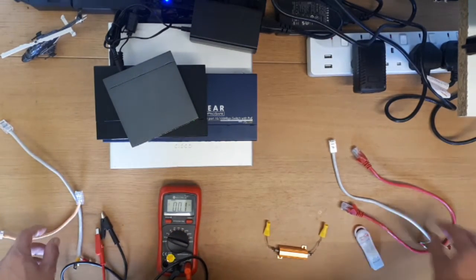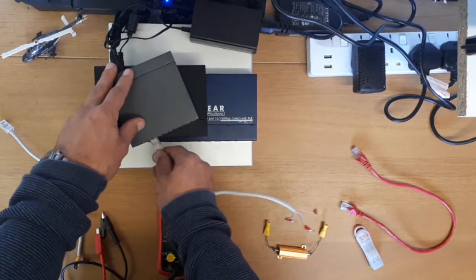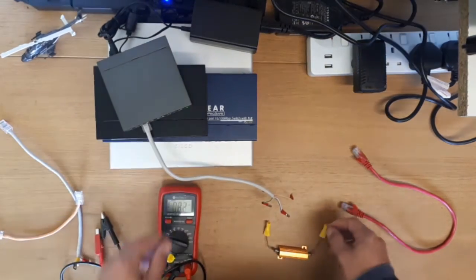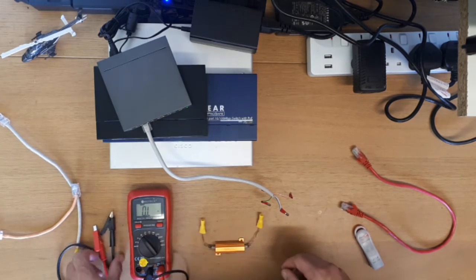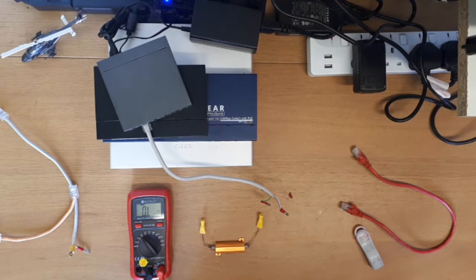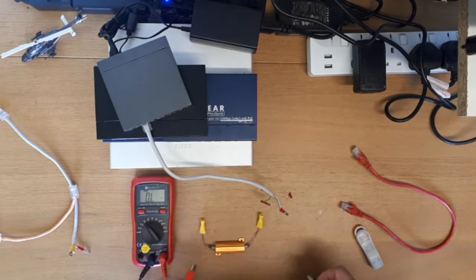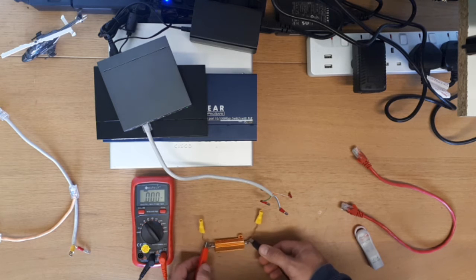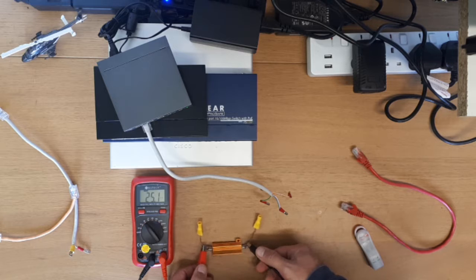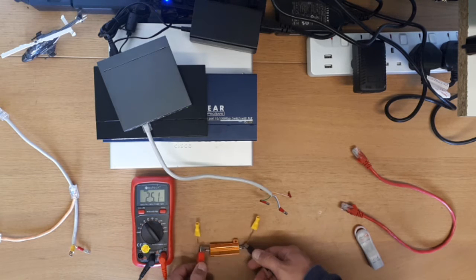So what we're going to do is connect this cable here. Now this resistor here is 25 kilohms. I've just turned this to resistance, and I'm going to demonstrate that this is a 25 kilohm resistor. Okay, 25.1 kilohms, which will meet this. I think 19 to 26 is the signal resistance that it has to drop between. It doesn't have to be exact.